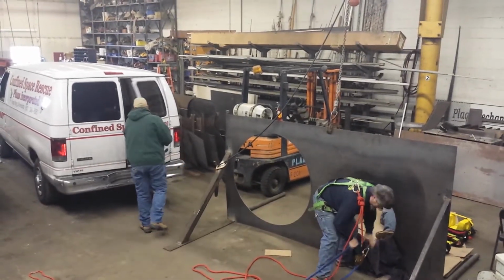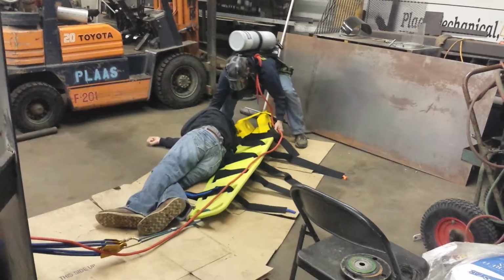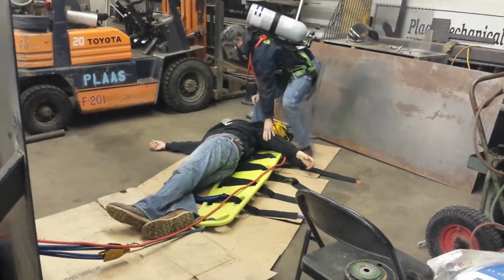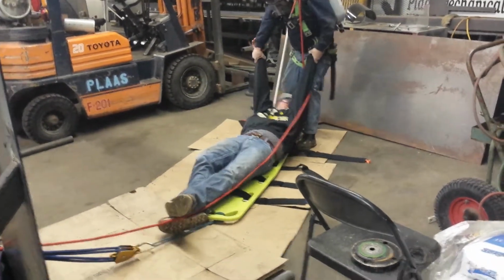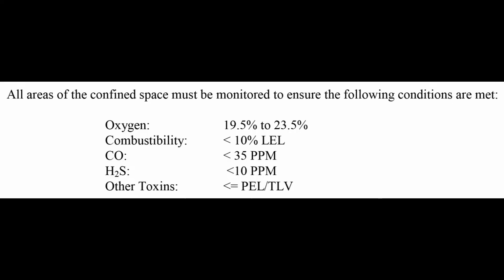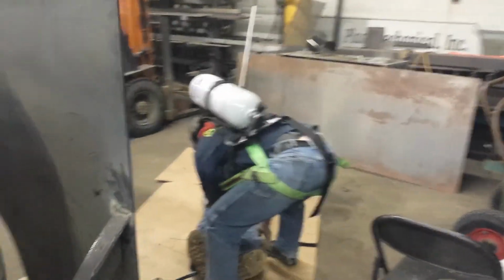For vertical entry confined spaces, the detector shall be lowered into the space to test each quarter section for 4 minutes in each position. The internal atmosphere shall be tested for the following conditions in the order given. 1. Oxygen content. 2. Flammable gas and vapors. 3. Potential toxic air contaminants. All areas of the confined space must be monitored to ensure the following conditions are met. Oxygen 19.5% to 23.5%. Combustibility under 10% LEL, CO under 35 ppm, H2S under 10 ppm, other toxins under or equal to PEL/TLV. If the monitor alarms at any time during testing, immediately remove the monitor and note the readings indicated, oxygen, combustible, CO, H2S, to determine which readings caused the alarm.